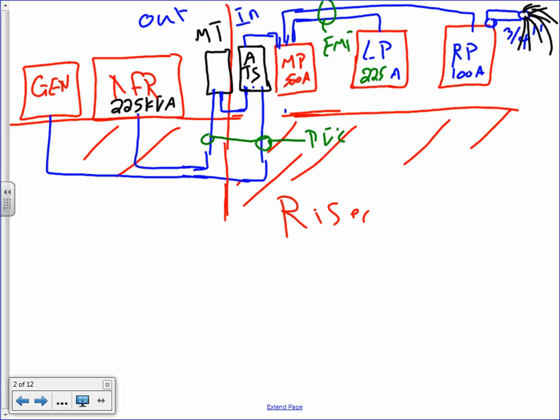Who cares if that was a one-line diagram with CAD? We don't care. We don't care in CAD. But in Revit, Joe, you need to actually pick a kVA size of the transformer when you drop it tomorrow. So can you guys pick 225? How did I come up with the 225? You take the 500, which is the size of the panel, multiplied by 208, multiplied by 1.73, divided by 1,000, gets you 180. The next standard transformer is 225 kVA. We don't size this, the utility sizes it. We're just dropping it in there, guys, so we can show a riser. Okay.